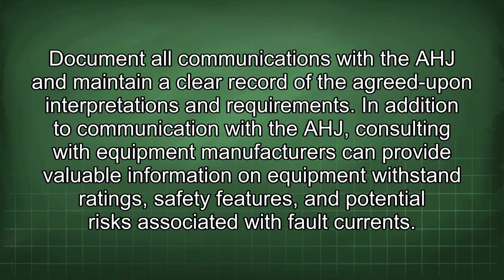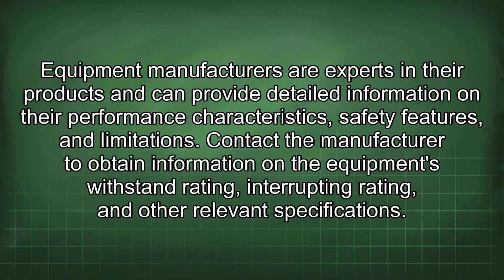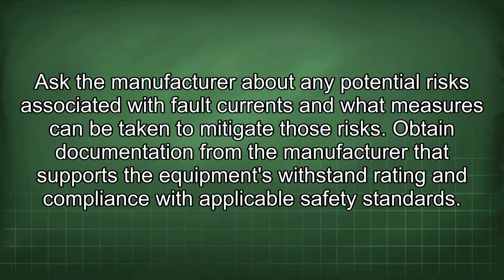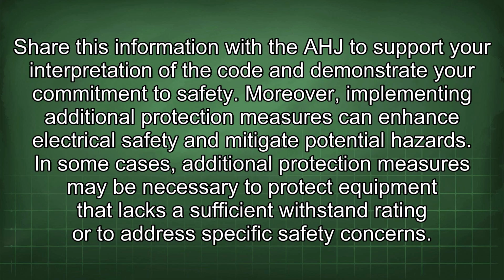In addition to communication with the AHJ, consulting with equipment manufacturers can provide valuable information on equipment withstand ratings, safety features, and potential risks associated with fault currents. Equipment manufacturers are experts in their products and can provide detailed information on their performance characteristics, safety features, and limitations. Contact the manufacturer to obtain information on the equipment's withstand rating, interrupting rating, and other relevant specifications. Ask the manufacturer about any potential risks associated with fault currents and what measures can be taken to mitigate those risks. Obtain documentation from the manufacturer that supports the equipment's withstand rating and compliance with applicable safety standards. Share this information with the AHJ to support your interpretation of the code and demonstrate your commitment to safety.